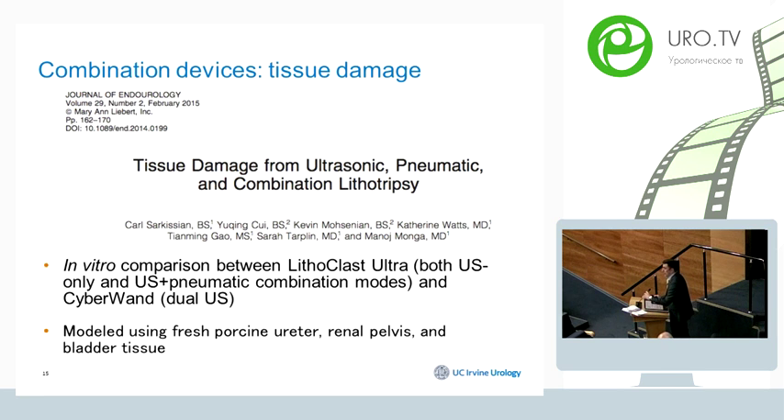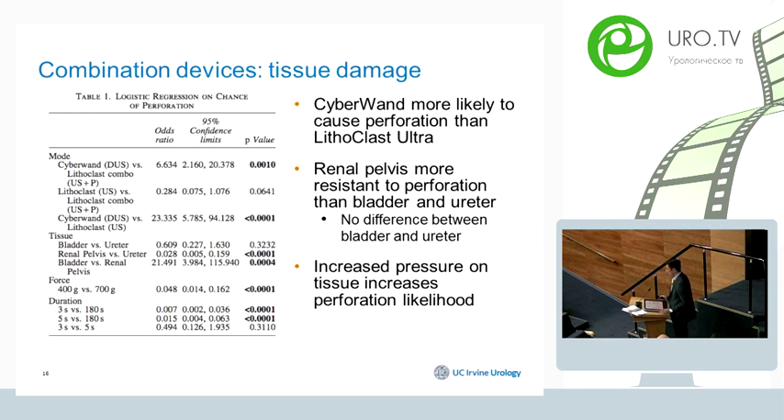Beyond efficiency and fragment size, an important factor in evaluating these devices is tissue damage. A study from Dr. Monga's group at Cleveland Clinic performed an in-vitro comparison of Lithoclast Ultra and CyberWand using porcine ureter, renal pelvis, and bladder tissue. The conclusion was that CyberWand was more likely to cause perforation compared to Lithoclast Ultra — a surprising result given how similar these combined devices are. They showed that increased pressure applied to tissue increases the likelihood of perforation.